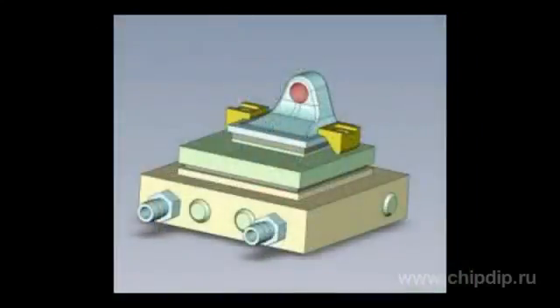The laser cooling system includes two heat-regulation water loops: one external and one internal. The heat exchanger ensures thermal interface between the coolers. This heat exchange system allows regulating operating temperatures within the range from minus 50 to plus 50 degrees Celsius.